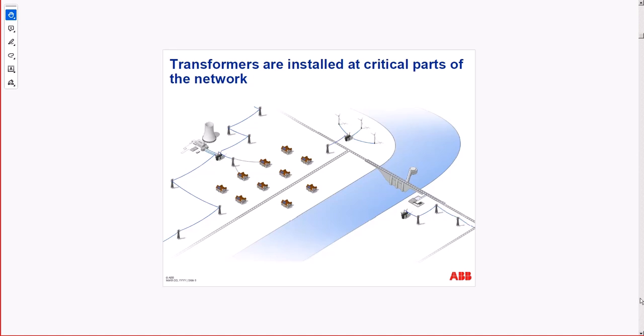Transformers are installed at critical parts of the network. Without the transformers, we don't have a network. Just about the big picture, you need a transformer stepping up the voltage from the generator. Usually generators are 20-plus kilovolts, and they go up, depending on the station, to 500 kilovolts for Darlington and Bruce, except units 1 and 2 at Pickering, which are 230 kilovolts. We need to step up the voltage on the high-voltage side because the transmission line needs a cross section supported by the current, so the current should be as low as possible for that power. Therefore we go with the voltage up. That's the reason for the step-up transformer right after the switchyard.